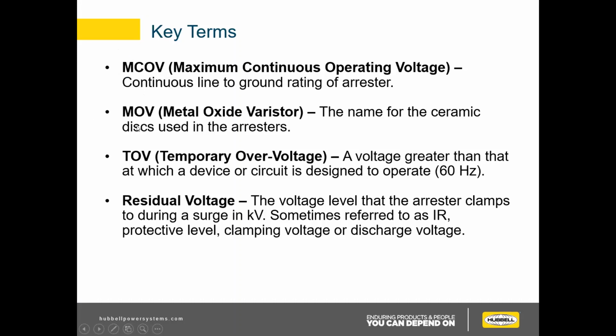MOV is metal oxide varistor. So that's the name for the ceramic disc that we use in the arrestor. So that, similar to the little red disc in the surge protector, these are kind of where the magic happens in arrestors in general. Next is TOV, which is a temporary overvoltage. So this can kind of get a little confusing at some points. But first, it's a voltage greater than that at which a device or circuit is designed to operate. And it's at a 60 hertz frequency. So a TOV is not to be confused with an impulse or a surge of any kind. This is something that's lasting for a tenth of a second or a couple seconds, where an impulse would be in the microseconds. So this is a system generated overvoltage, not to be confused with an impulse.